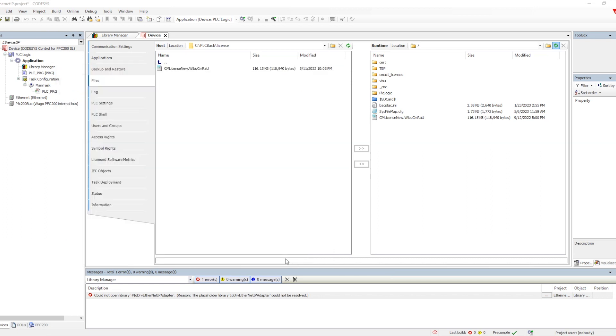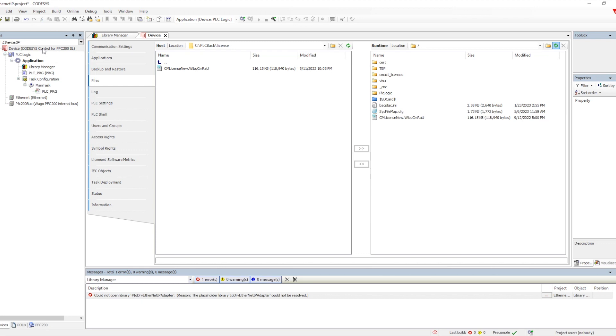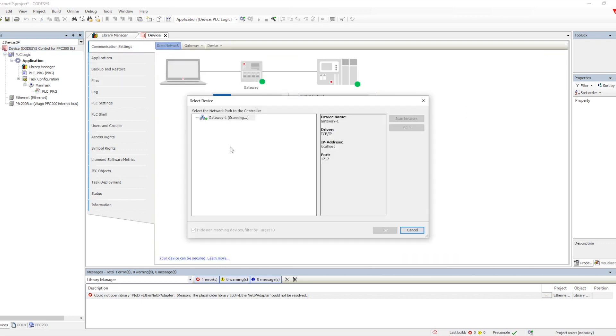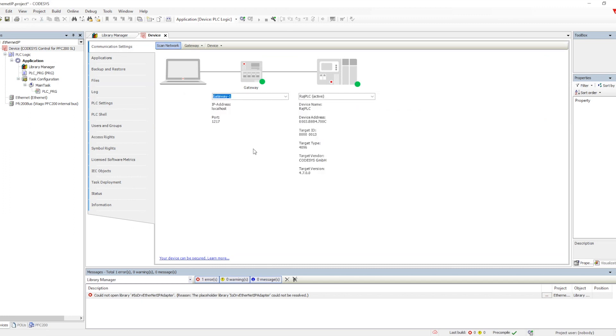Once the firmware got updated we can connect to the PLC using the web server. One thing you should always take care is always backup all your items from the PLC because when we upgrade the firmware it removes all the files. Right now you see I am not able to scan any of the hardware even if it is connected.